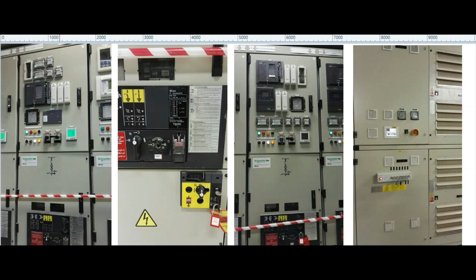Now I will show you this 6.6 kV switch gear modules. So unlike LV modules, here in 6.6 kV each vertical panel there is only single module. So you can see in the first snap, in the topmost compartment is the control, and this is the control compartment, control cabinet. All the meters, relays are installed here, and also the selector switch, local remote selector switch, control switch, indicating lamps.